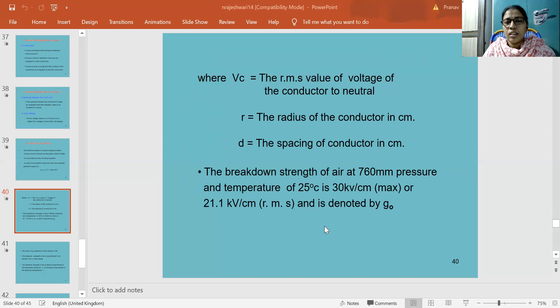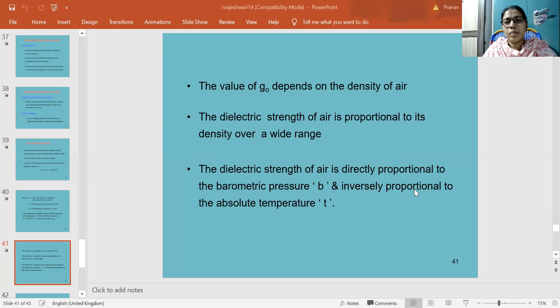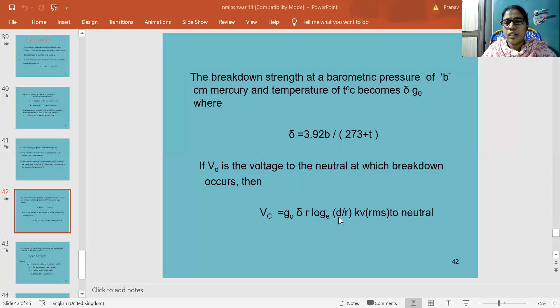And the value of g naught depends on the density of air. The dielectric strength of air is proportional to its density over a wide range, and is directly proportional to the barometric pressure b and inversely proportional to the absolute temperature T. The breakdown strength at barometric pressure of b centimeters of mercury and temperature of T degrees centigrade becomes delta g naught, where delta is equal to 3.92 b by 273 plus T. So if VD is the voltage to neutral at which breakdown occurs, then the critical disruptive voltage Vc is equal to g naught delta r log d by r kV RMS to neutral.